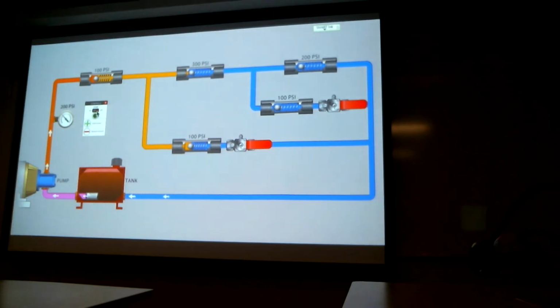I'm going to turn the pump off. And now I'm going to close this shutoff valve to make it a path of very, very high resistance. Take a moment to have a look at this circuit. Where do we expect our next flow path to be? Estimate what you believe the system pressure will be when I turn the pump back on.